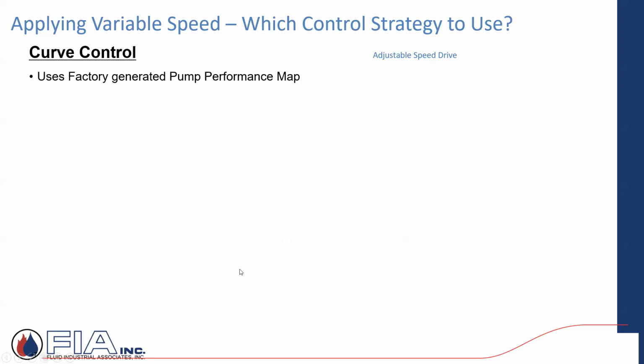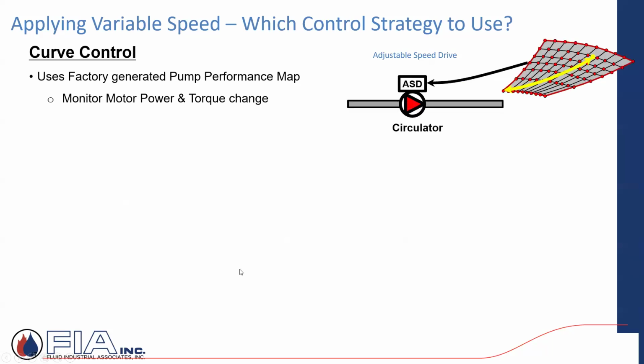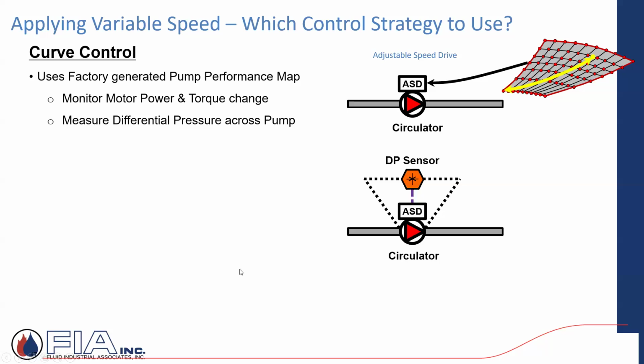Applying variable speed control strategies, curve control. They'll call it that factory generated pump performance map, where they have this adjustable speed drive. Maybe it's right on board the pump, and they might be referred to as sensorless. So it's monitoring motor power and torque change. You might have a DP, so differential pressure sensors across the suction and discharge just right at the pump. That's information that can feed back to this adjustable speed drive, this ASD, that's going to influence the speed of that pump based on system conditions. So these things are set up on commissioning. And then as the system's operating and things change, it reacts and changes the speed of the pump to reduce. At the end of the day, what we're doing is trying to prevent wasting energy. Change the speed, change the electrical consumption.